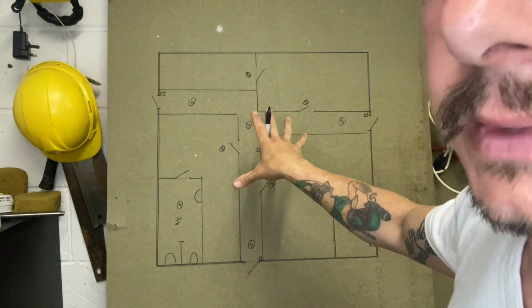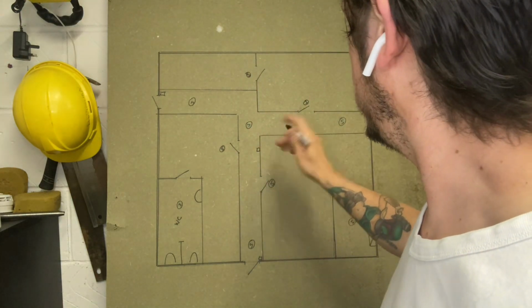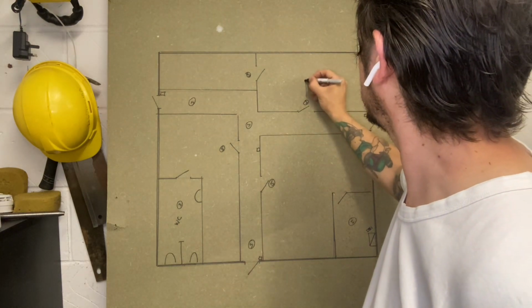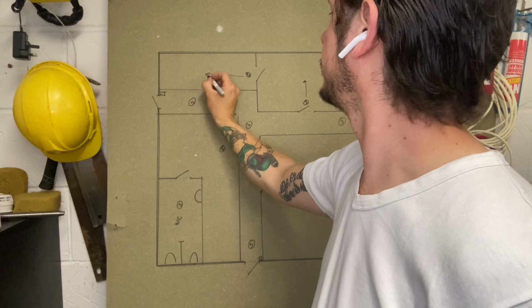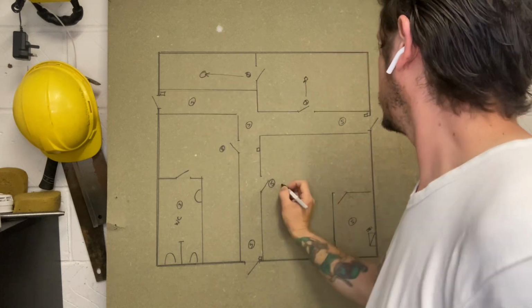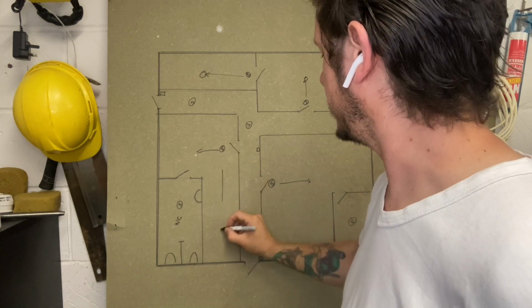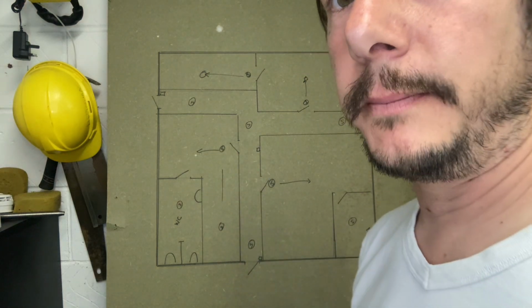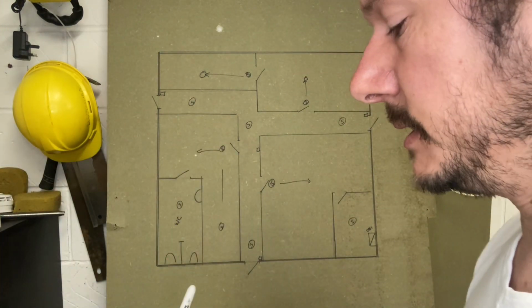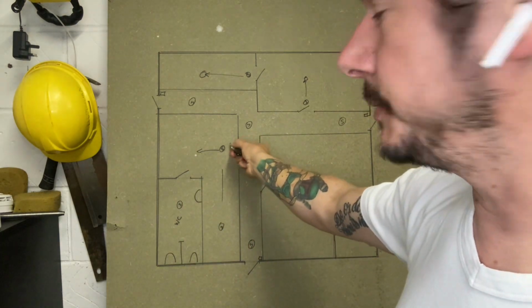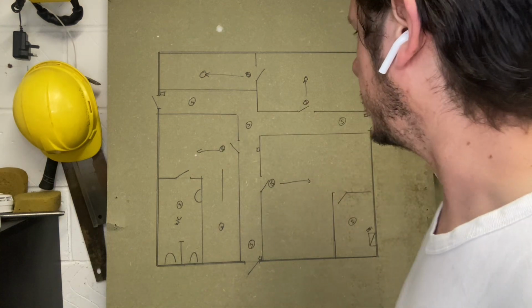The giveaway on an L1 on an existing system is that these detectors covering the doors are suddenly in the middle of the room, because we are covering these whole areas. In fact, you probably want another one down there somewhere. So the L1 is you're covering the rooms. It's not just the escape route, you're covering everywhere. Therefore, we're not focusing on the door, we're doing the whole area.